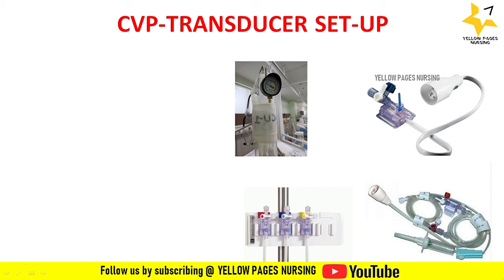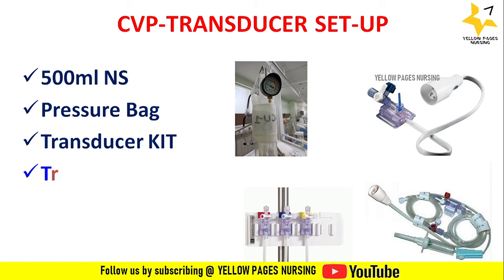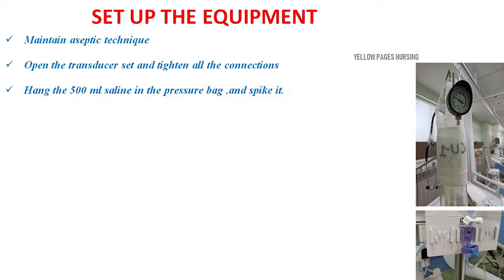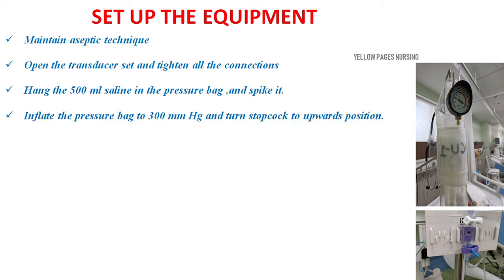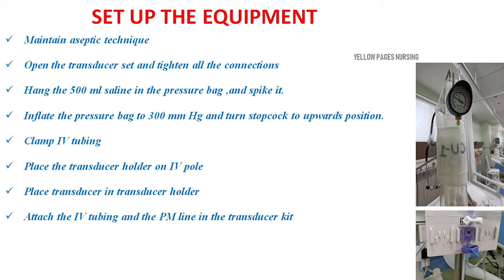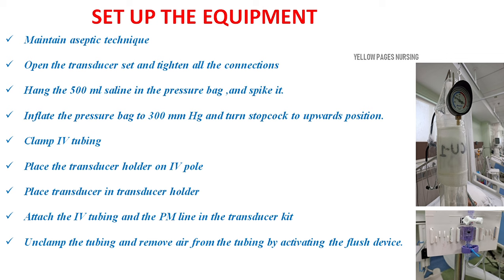For the central venous pressure transducer setup, the articles needed are: 500 ml normal saline, transducer kit, transducer holder, and transducer pressure cable. To set up the equipment: maintain aseptic technique, open the transducer set and tighten all connections, hang the 500 ml saline in the pressure bag and spike it, inflate the pressure bag to 300 mmHg and turn the stopcock to the upwards position, clamp IV tubing, place the transducer holder on the IV pole, place the transducer in the transducer holder, attach the IV tubing and PM line in the transducer kit, unclamp the tubing and remove air by activating the flush device, then point the stopcock at the transducer horizontally and clamp the tubings.